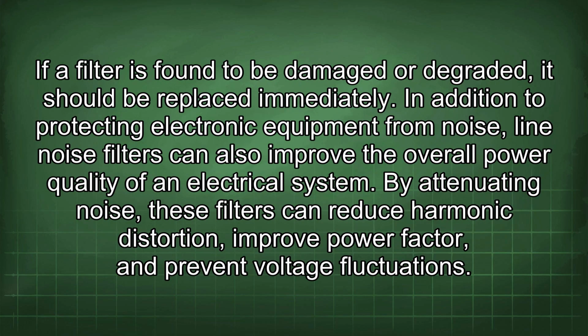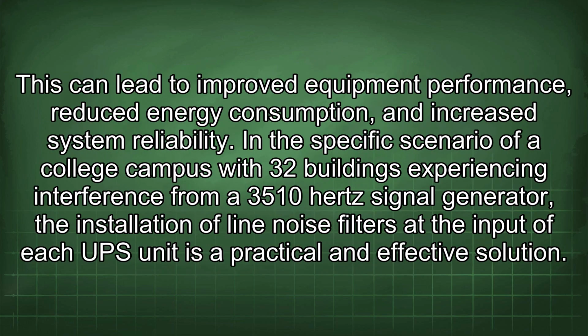If a filter is found to be damaged or degraded, it should be replaced immediately. In addition to protecting electronic equipment from noise, line noise filters can also improve the overall power quality of an electrical system. By attenuating noise, these filters can reduce harmonic distortion, improve power factor, and prevent voltage fluctuations. This can lead to improved equipment performance, reduced energy consumption, and increased system reliability.